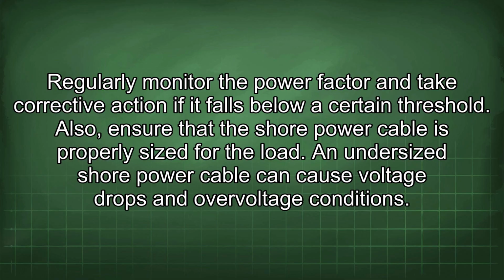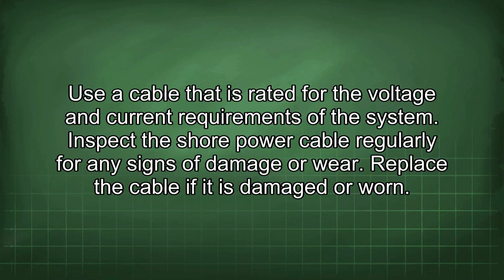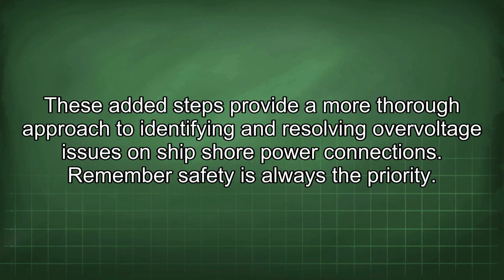Also, ensure that the shore power cable is properly sized for the load. An undersized shore power cable can cause voltage drops and overvoltage conditions. Use a cable that is rated for the voltage and current requirements of the system. Inspect the shore power cable regularly for any signs of damage or wear. Replace the cable if it is damaged or worn. These added steps provide a more thorough approach to identifying and resolving overvoltage issues on ship shore power connections. Remember, safety is always the priority.